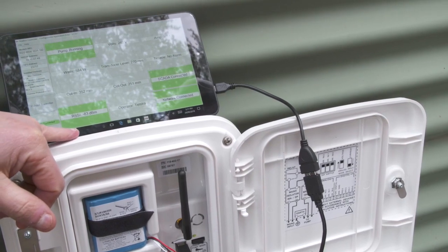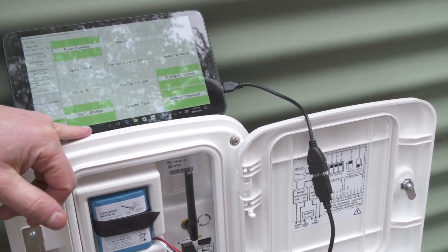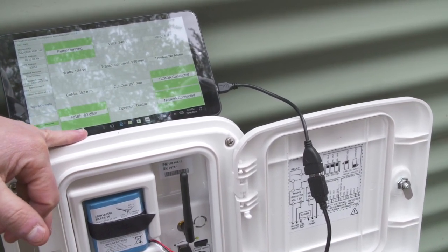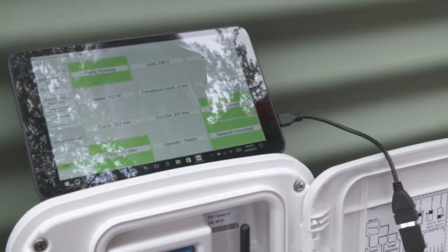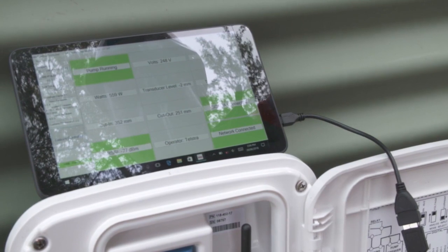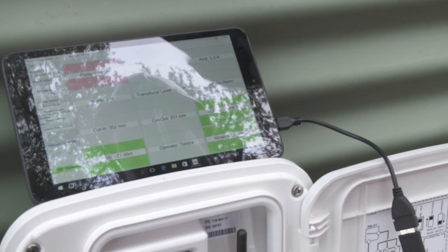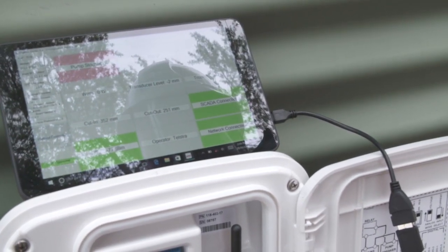Note the voltage for records. The network connection and SCADA connection should turn green indicating successful connection. This may take a few minutes. Turn the test switch from normal to test. This provides power directly to the pump. Note the current draw in amps, which confirms the pump is working correctly and drawing expected amps. Turn the test switch back to normal. Note that the pump running indication on the tablet will not register in test mode.